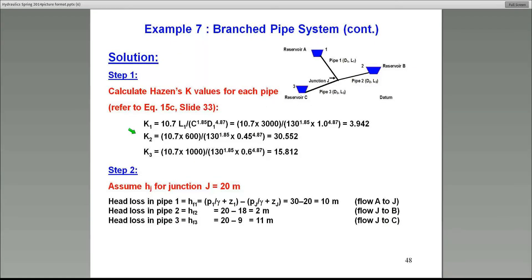So the first thing we're going to do is calculate all the K values. That's in all hydraulic problems, pipe problems, this is the first step always. This is in SI units, so I use the formula 10.7: L divided by C to the power 1.85, and D to the power 4.87, all in consistent units. In this case, K1 is 3.942, K2 is 30.552, K3 is 15.812. Now remember, you have to do this computation accurately because there's no way to verify these numbers whether they're right or wrong.